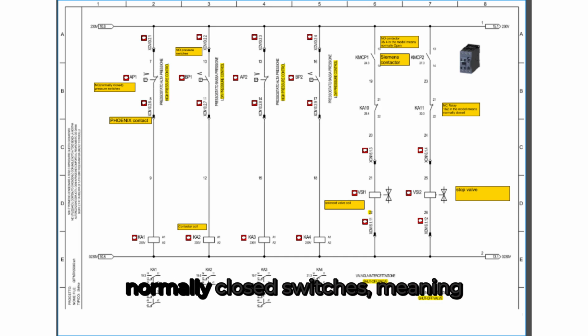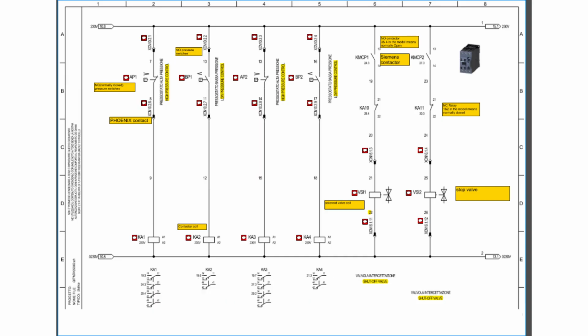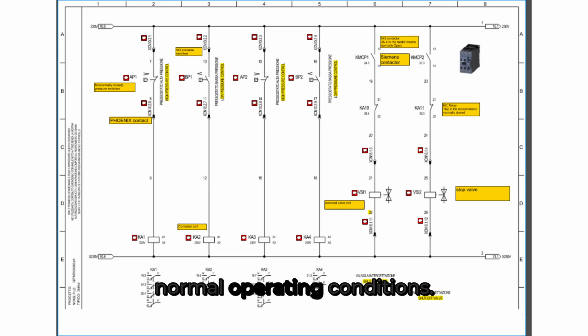High pressure switches are normally closed switches, meaning they stay closed under normal operating conditions. If the refrigerant pressure goes too high, the switch opens the circuit to protect the compressor from damage. Low pressure switches are normally open switches. When the pressure reading is below the threshold, it closes the contact and sends an alarm signal.